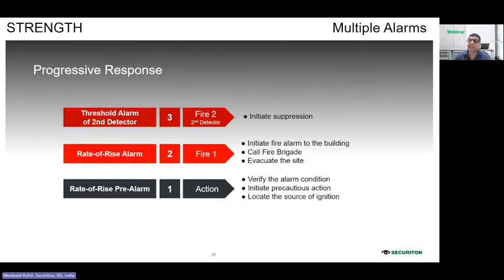Multiple alarms in the ADW 535 are possible. You have action, fire 1, and fire 2. It depends on how you program it, because it is field programmable. The action alarm is triggered when the system detects unusual heating but not yet at fire threshold. You can use the initial alarm for the main fire alarm system and fire 2 when it is required to trigger the suppression system. So different permutations and combinations are possible.